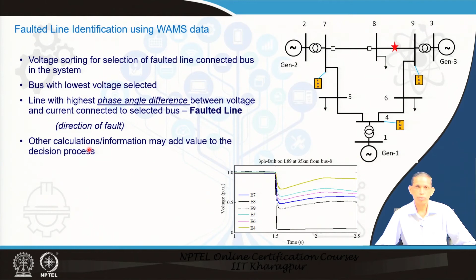We have 3 PMUs and a fault happens to be there between bus 7 and 8. At that time we collected data in the simulation process. At bus 4, bus 7 and bus 9, these are the PMU data, positive sequence data, for a 3 phase fault. So, E4, I46, I45, the corresponding lines. At bus 4 we have 2 lines, 4 5 and 4 6, and these are the associated currents. At bus 7 we have 2 lines, this line and this line, and at bus 9 we have 2 lines, 9 8 and 9 6. All currents associated with those PMUs are also available, including the voltage. So, 3 voltages: 291, 115 and 210. The minimum one is 115, so we bring out bus 7 as the choice of the lowest voltage bus.